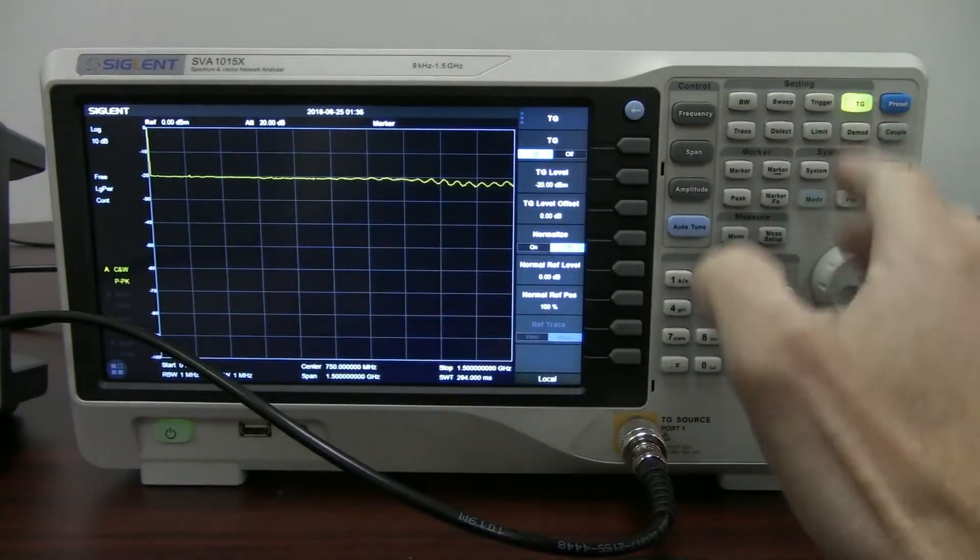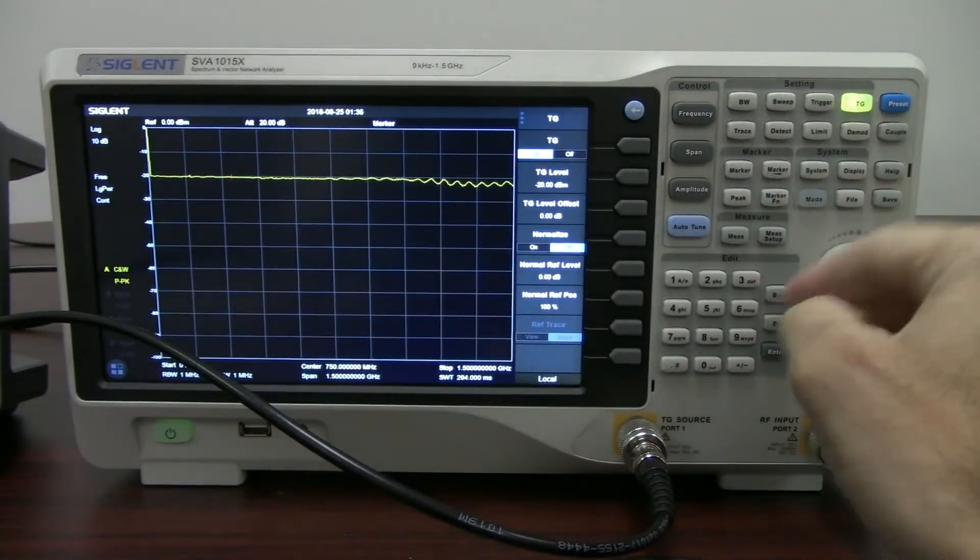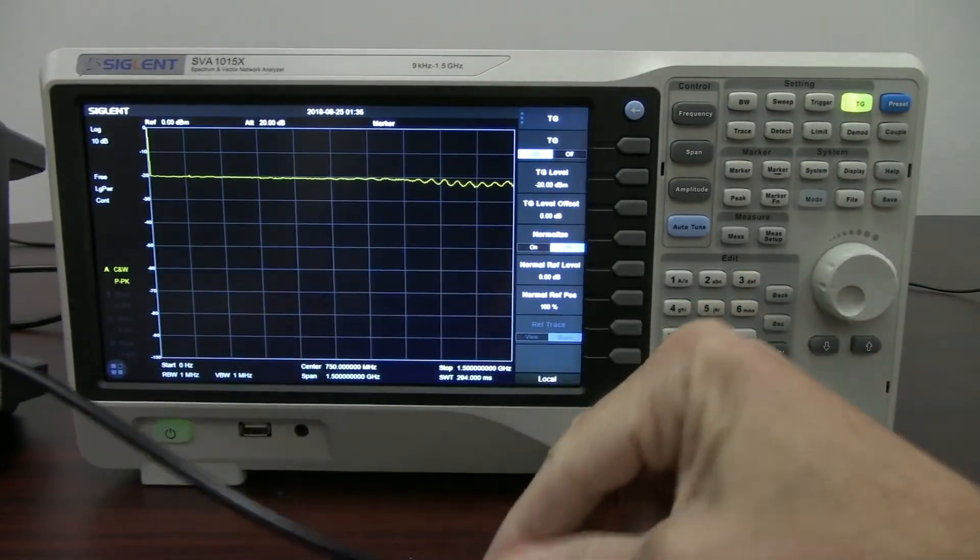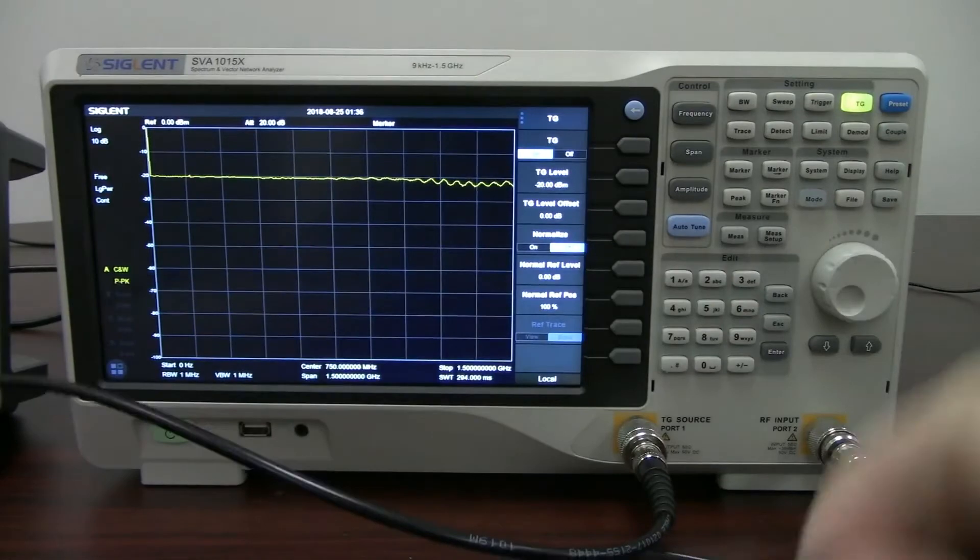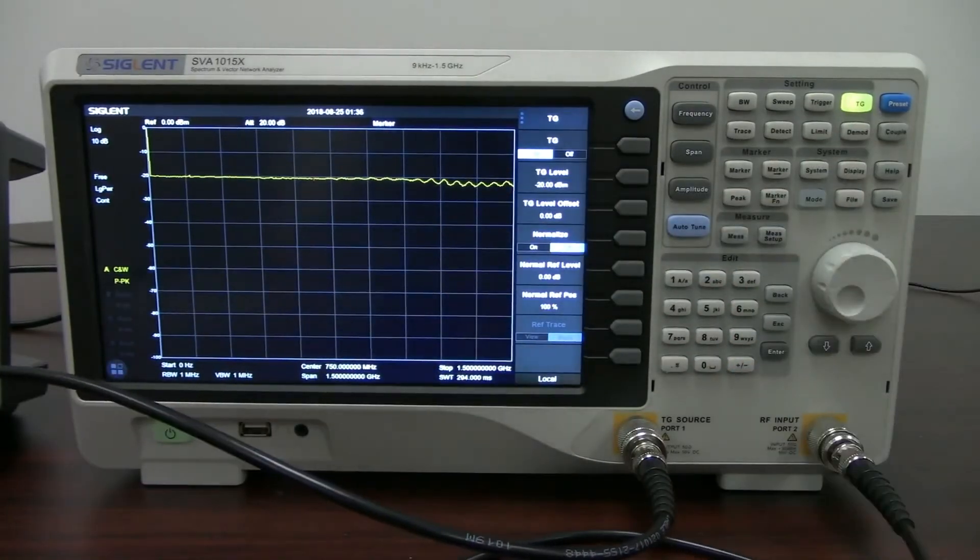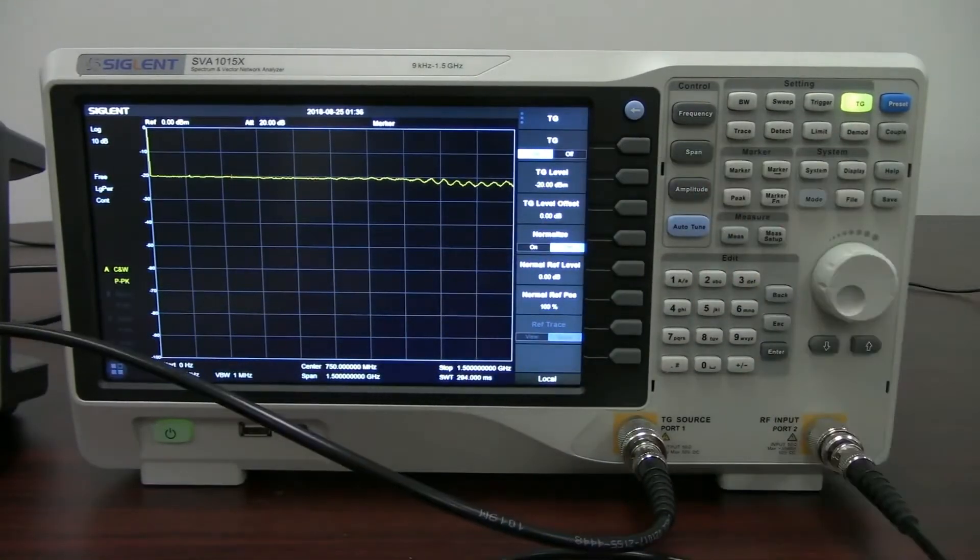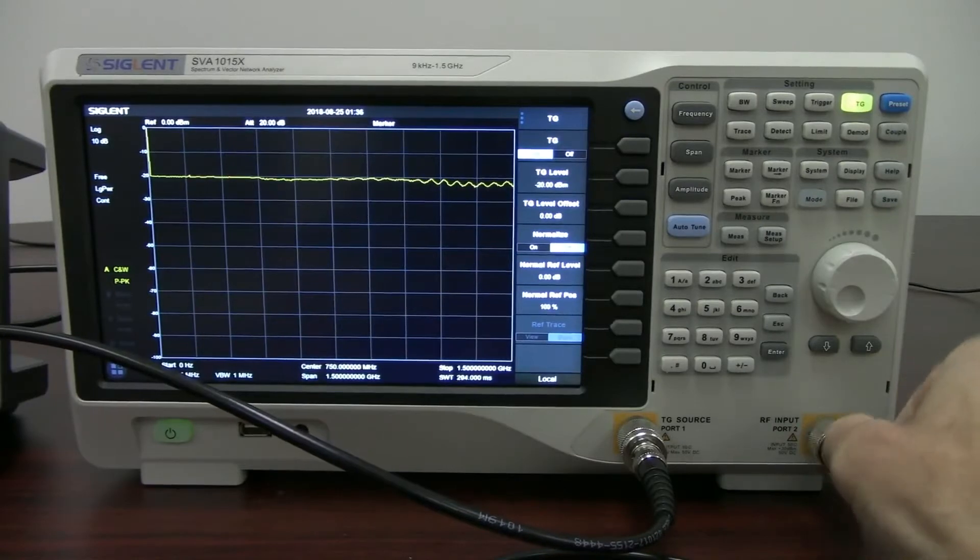A lot of the ripples and things that you see are totally normal. They're within specifications. Some of them are due to cable effects as well as the adapters. We actually want to get rid of everything in this system, or all of the errors that are being caused by the cabling and the adapters.